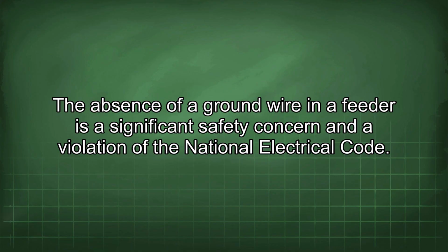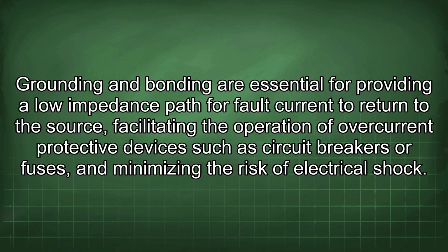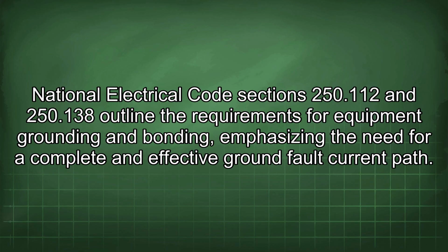Grounding and bonding are essential for providing a low impedance path for fault current to return to the source, facilitating the operation of overcurrent protective devices such as circuit breakers or fuses, and minimizing the risk of electrical shock. National Electrical Code sections 250.112 and 250.138 outline the requirements for equipment grounding and bonding, emphasizing the need for a complete and effective ground fault current path.